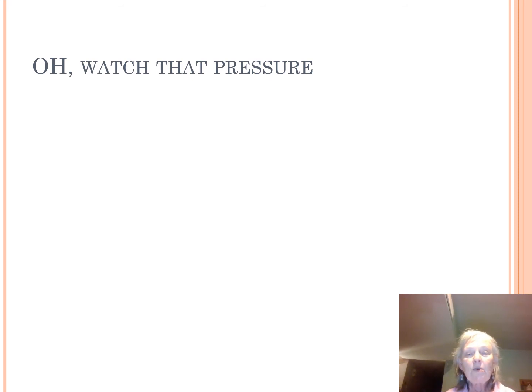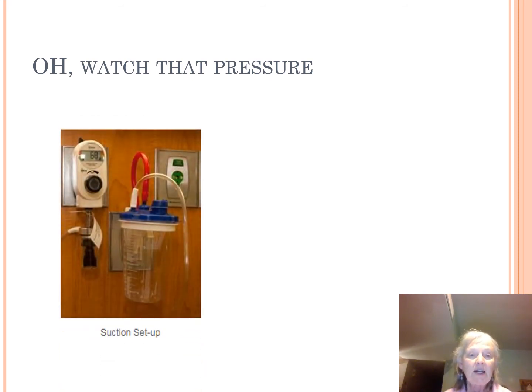So in this case, we're going to have to watch that pressure. This is a setup. As you can see, there's a regulator here. We'll grab our little pointer. Our little pointer, there we go. And here's your suction canister at this particular point. You can see some of the suction tubing. This is the tubing that is actually connected to the suction port, the regulator at this point. And so here's your regulator. That's going to go ahead and regulate the pressures for us. Over here is your DISS outlet. This is oxygen, remember? And then we're going to be able to go ahead and hook these patients up to oxygen then.